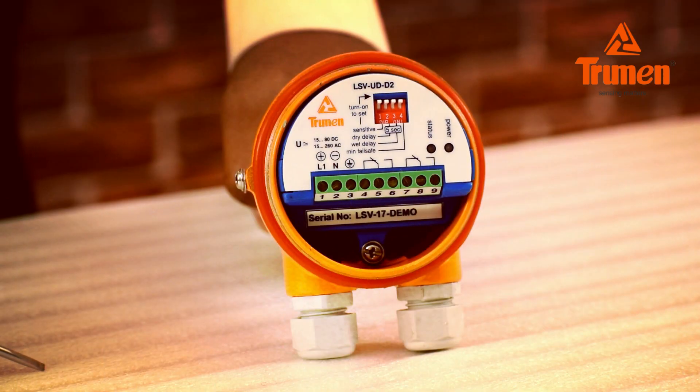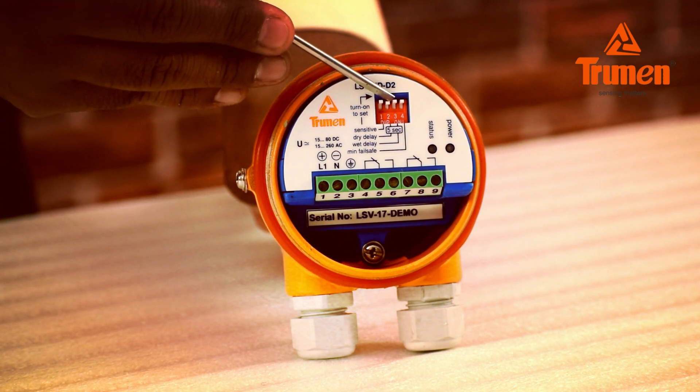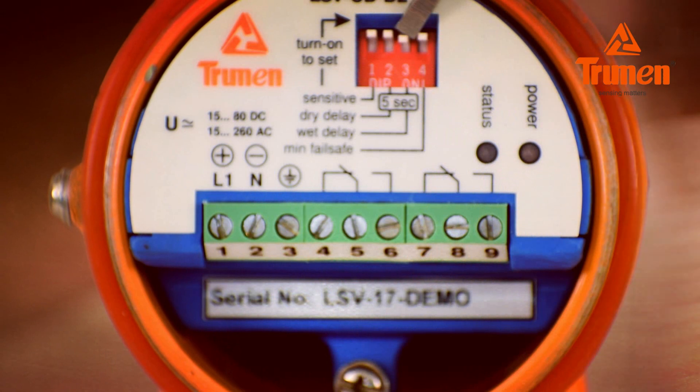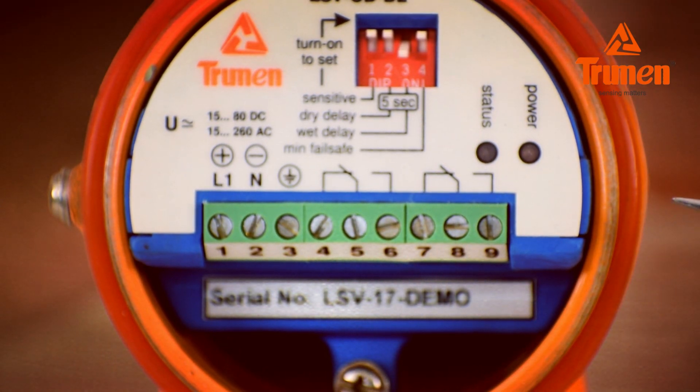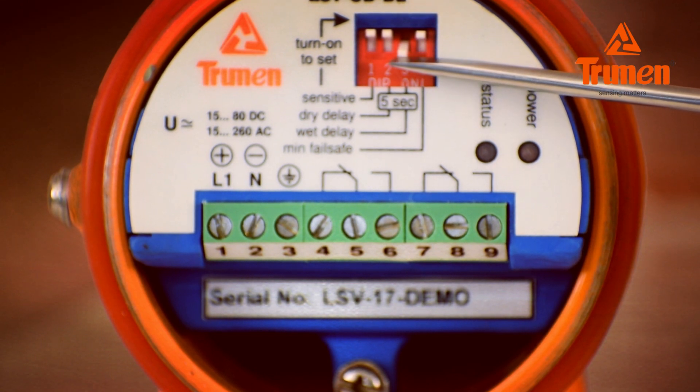Switch number 2 sets the dry delay, meaning off delay — the sensor will wait for 5 seconds once the material goes below the sensor. Switch number 3 sets the wet delay, meaning on delay — the sensor will wait for 5 seconds once the material touches the sensor.